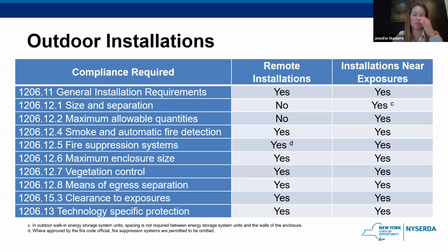And the compliance that is required for those varies based on whether they're near exposures or remote. Again, you'll see mostly yeses here to those requirements. The ones that stick out as no's are that remote installations, not near anything else, do not have to adhere to the size and separation requirements, nor do they have to adhere to those maximum allowable quantities.